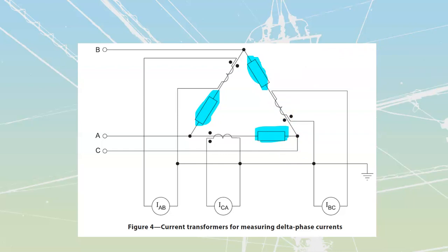Note that I've got my polarity dots highlighted to line up: this one lines up with B, this one lines up with A, and this one lines up with my C line over here, that node. We maintain polarity all the way around because if I flip one of these CTs around, we'll get false readings. Just treat these dots as if they were arrowheads - we've always got an arrowhead going through.